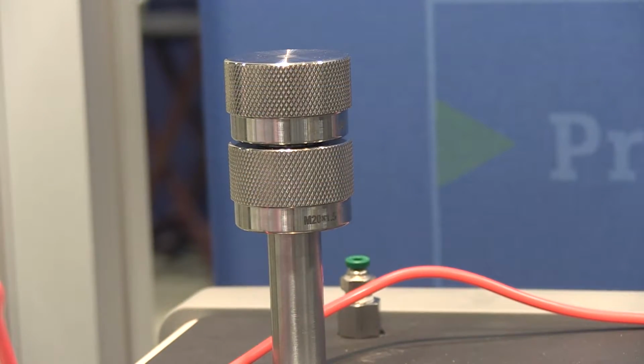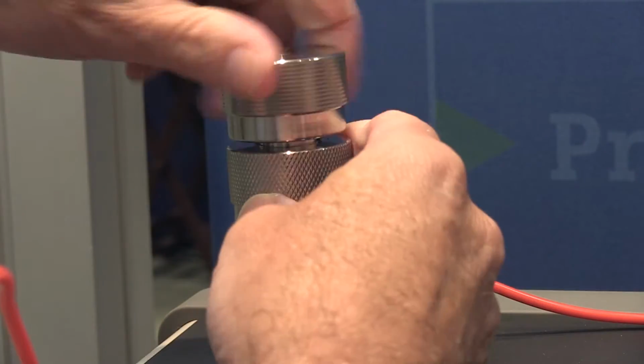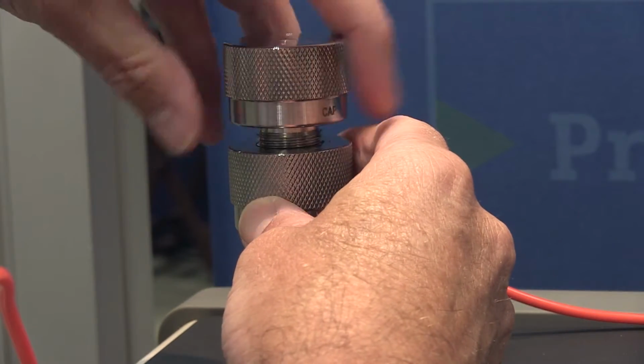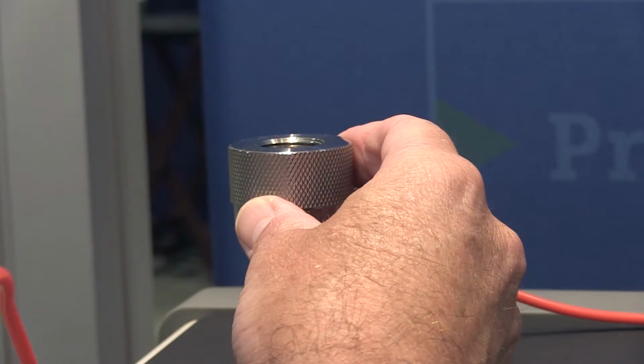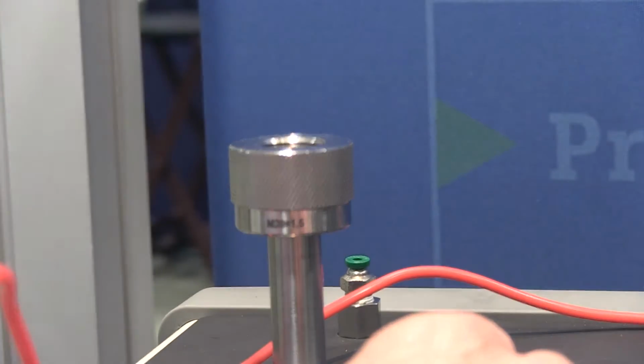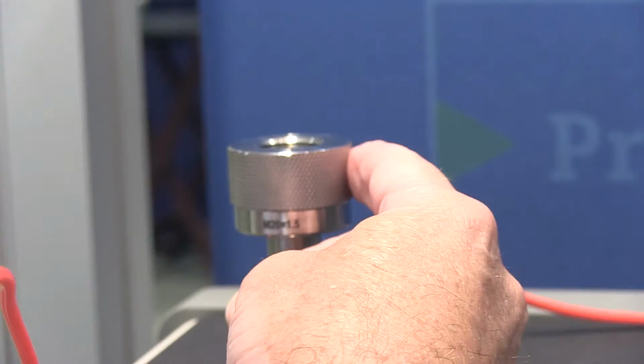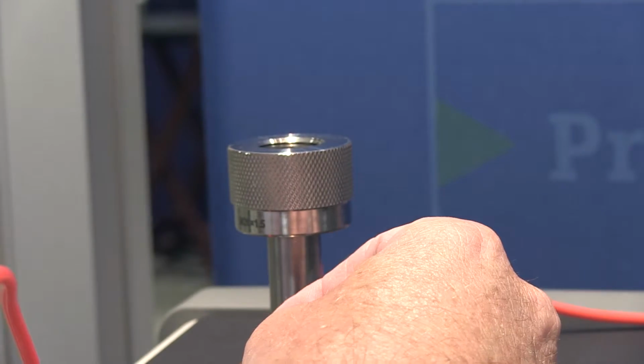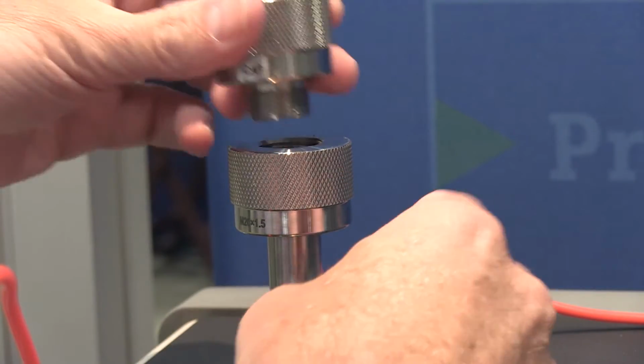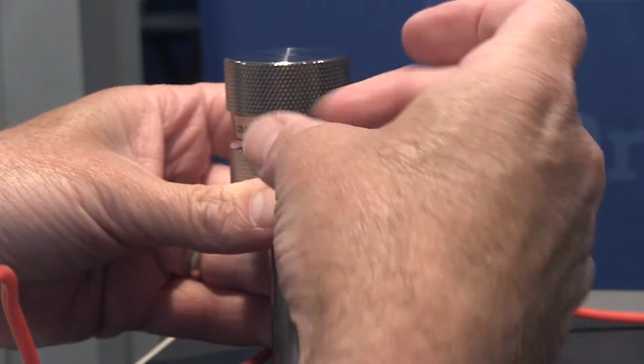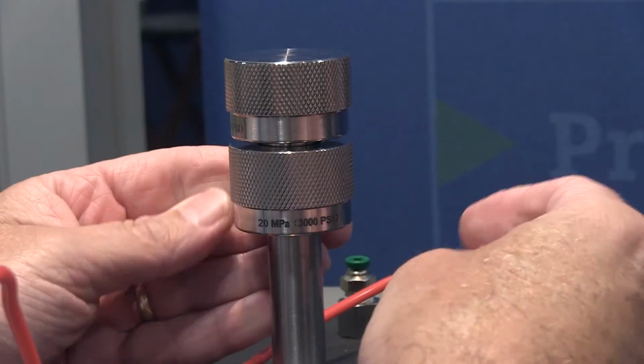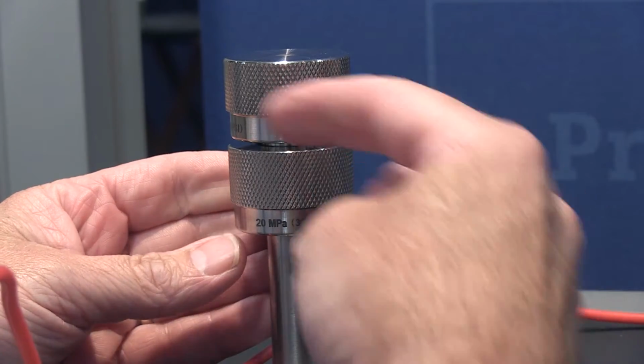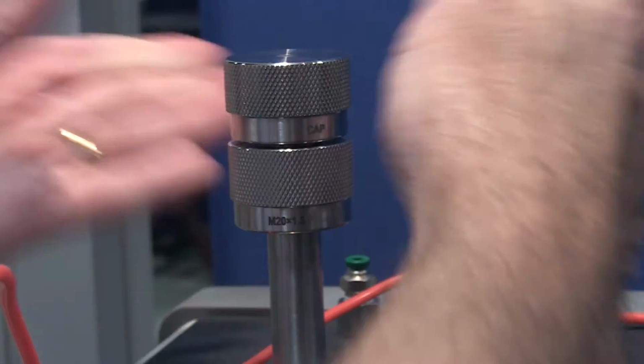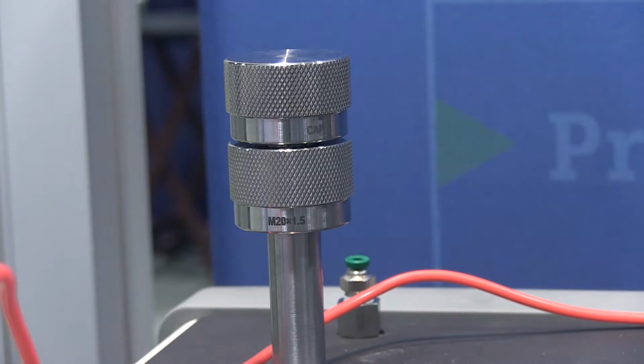So new to the 2271A is a hand-tight quick connect adapter, a new design that doesn't require any sealants or Teflon tape. This is just a plug that's screwing into it. It's an M20 thread on this particular one, but they have NPT and BSPs available as well. So you just take your gauge or transmitter that you would like to calibrate, screw it in, snug it down, and it's hand tight to the full working pressure of the unit, which is 3,000 psi.